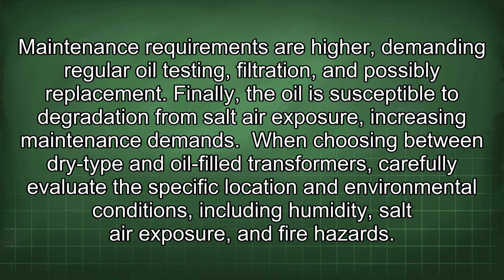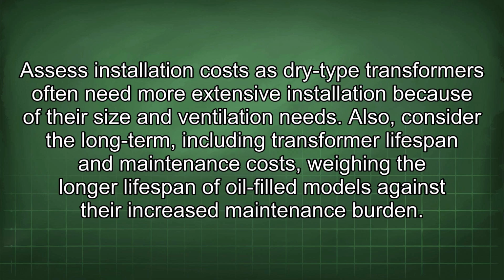When choosing between dry-type and oil-filled transformers, carefully evaluate the specific location and environmental conditions, including humidity, salt air exposure, and fire hazards. Assess installation costs, as dry-type transformers often need more extensive installation because of their size and ventilation needs. Also, consider the long term, including transformer lifespan and maintenance costs, weighing the longer lifespan of oil-filled models against their increased maintenance burden.